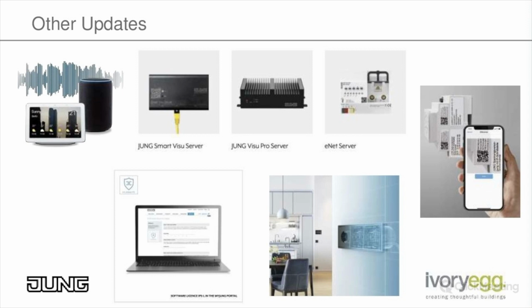Another one is a new app which enables you to get KNX secure devices into ETS really quickly. KNX devices that use KNX Secure come with a pre-shipped factory key, which is stamped on the side of the product, and it's normally available as a card as well. You have to enter that information into ETS. Now you can use a USB scanner or the camera of the device, or type the very, very long string yourself. Or you can just use the Jung app, take a photo of the QR code, and then there's an app you need to install in ETS. Once you've got both running, it will automatically sync and populate those codes into ETS. So it's a really simple way of saving a bit of time with your commissioning if you're doing a secure installation.